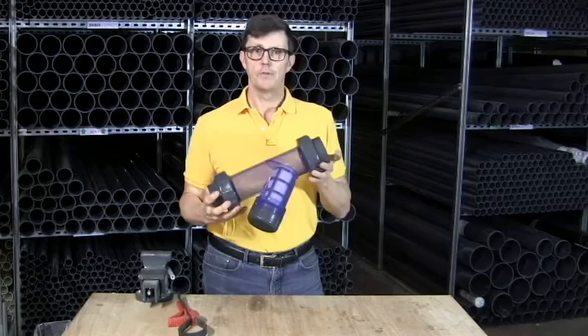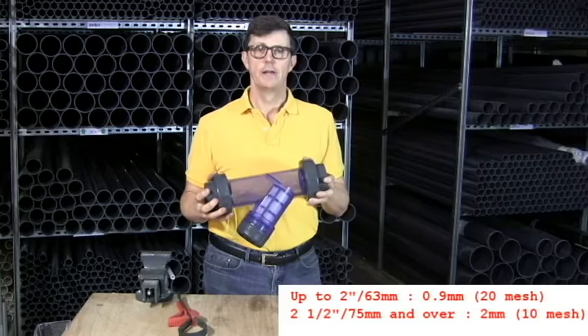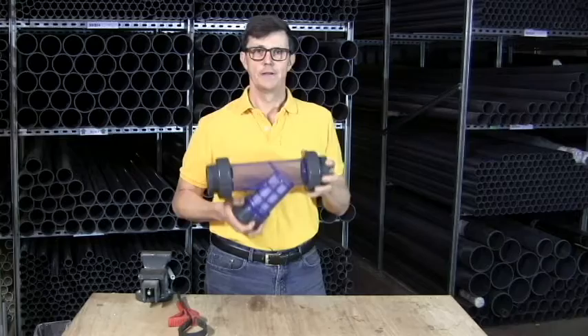The Y strainers are available from 20 millimeters or half inch right the way up to four inches or 110 millimeters. Up to two inches in size they'll take out particles 0.9 millimeters and larger, and the sizes of two and a half inches and above — that's 75mm and above — will take out particles of two millimeters and larger. So it's a 0.9 millimeter mesh up to two inches and 63mm, and a two millimeter mesh from two and a half inches, 75mm and above.